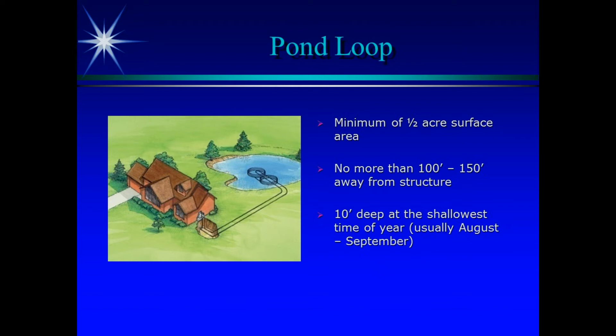Does that make sense? So you put these pond loops in about 10 feet down or more, but the pond has to be no less than 10 feet deep at the shallowest time of year, which is usually around now, August, September, October, before the October rains. That's about when the pond's at its lowest. The reason is, if it gets any shallower, we don't have enough BTUs of water there. We're going to run out of BTUs. So for instance, if we're heating, like in the wintertime, and we don't have enough BTUs in the pond, I'm going to turn the whole pond into ice.